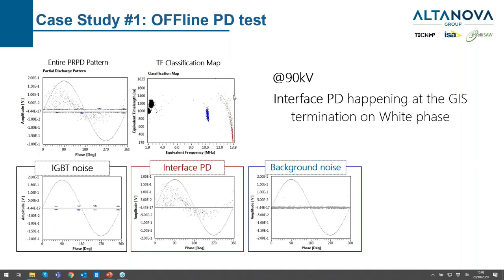When the test started and 90 kV phase-to-ground voltage was injected, we could see a strange signal. From the entire PRPD you could see a cluster of points — very high amplitude but not many, with a low repetition rate, following the applied voltage signal somewhat. The time-frequency classification map was able to select a different cluster of points. The red cluster was the PD triggering our attention as an interface PD — a kind of surface partial discharge.